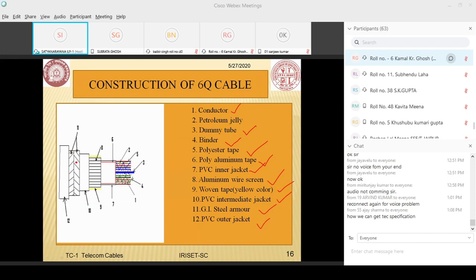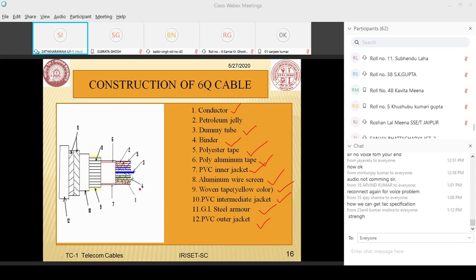What is the purpose of the dummy tube? The dummy tube fills the gap in the circumferential arrangement, making the structure perfect. If you see, the conductors are arranged in a circumferential, geometrical fashion. It also gives additional mechanical strength. Basically, the dummy tube fills the gap in this arrangement.